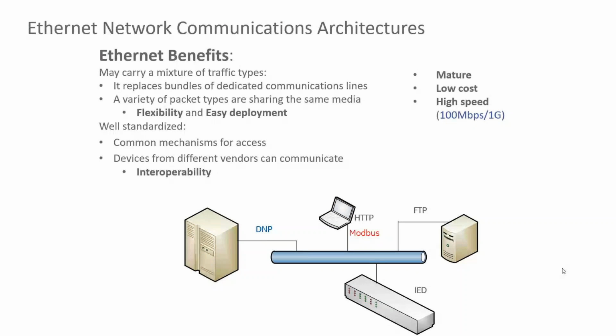Well, I shouldn't say all - most protocols are supported over Ethernet. So you could talk DNP, you could talk Modbus, having different devices on the Ethernet network with different protocols, and they can all talk back to your SCADA master, no problem, over the same data link.